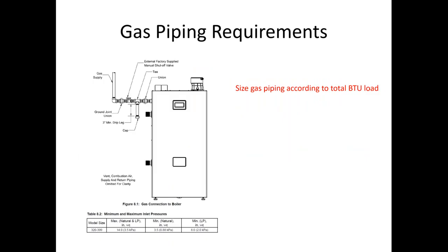The 320 and 399, you're going to be able to do about 3.5 inches of water column. That is going to be the minimum that those products will run with. And again, it's a 400,000 BTU gas appliance. We're going to need to size it accordingly, size the gas lines properly for the unit.